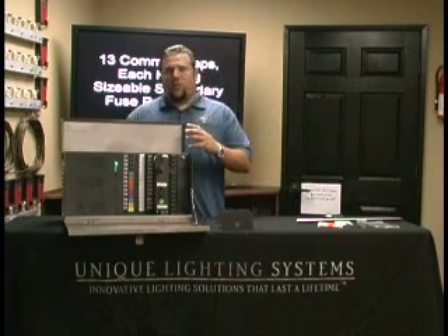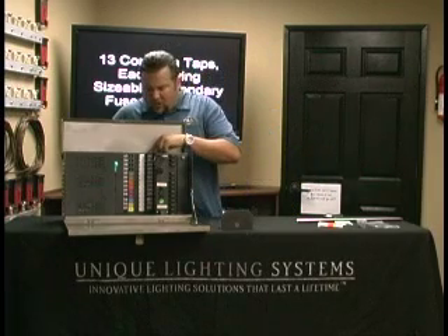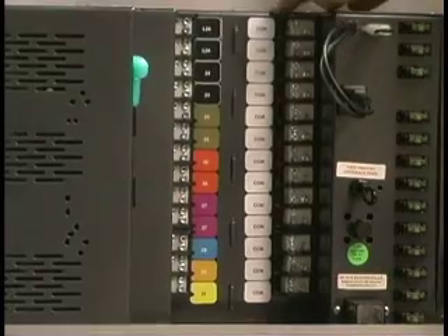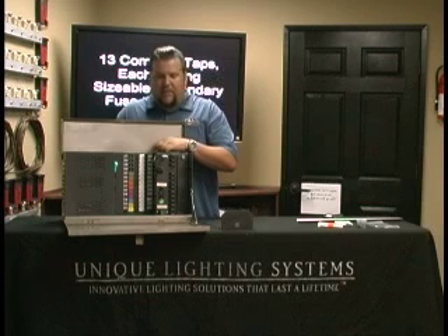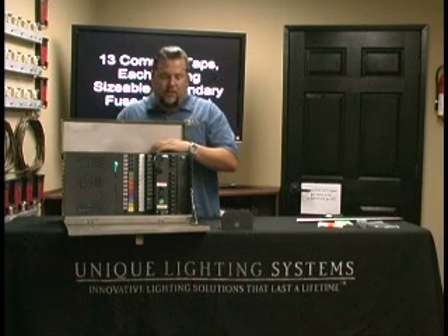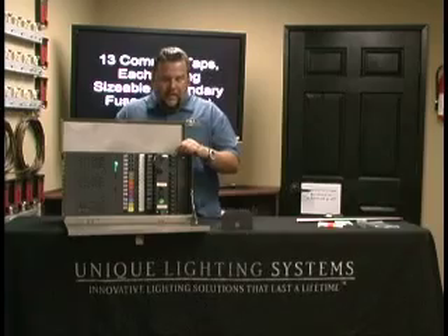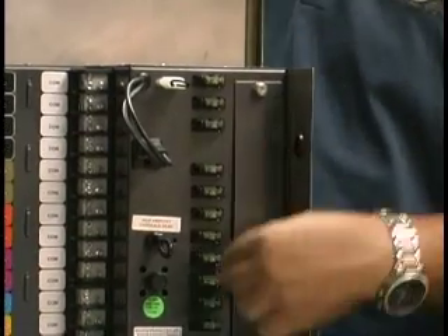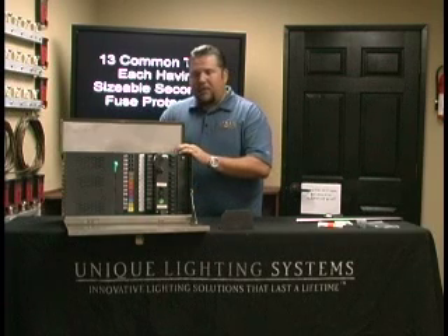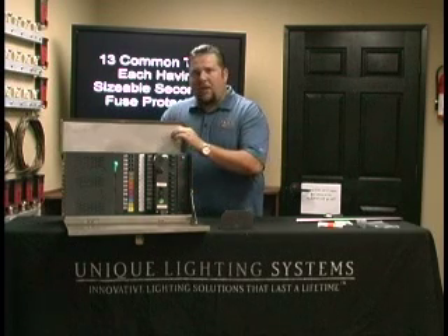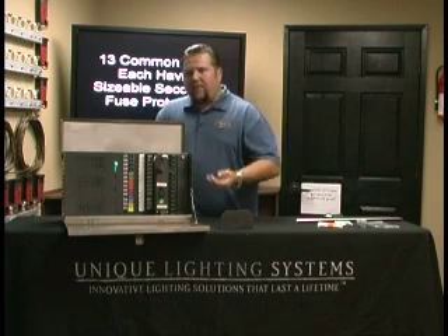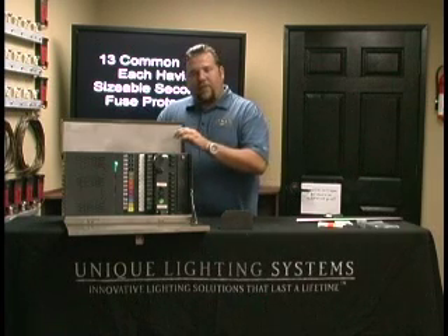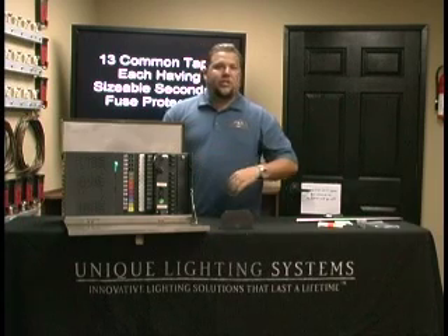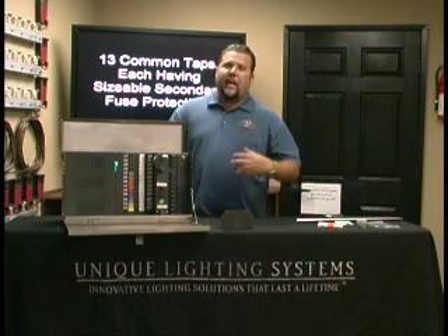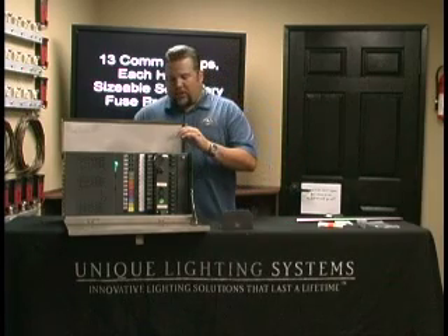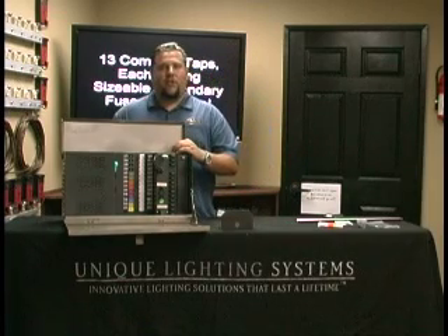The transformer, what makes this really cool is its multiple common taps. So you can see here there's 13 common taps available on the H-Force. Every size unit will have all of these common taps on here. And to the left here, you can see that each common has its own secondary fuse. This is huge because this gives you now the ability to fuse per load on each common you have running on the transformer. So for every secondary wire run you pull in, you can do your fusing right here at the transformer. Of course, you can still fuse at the hub if you prefer to do so and have double the protection. But this is going to be the biggest feature, in my opinion, for this transformer.